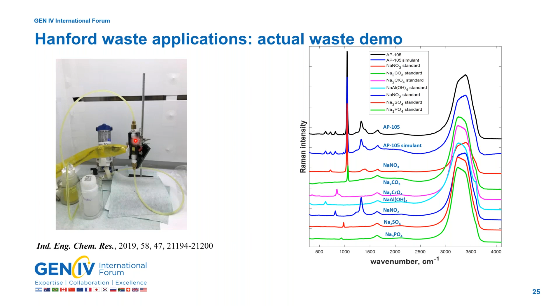So we've taken this AP105 and we put it in one of our flow cells, or in a flow loop. This is the AP105 waste here. It's straight AP105 waste. It's not been processed in any way except to take the cesium-137 out by ion exchange so we can have it contact handled in our open-face rad hood. So we have a pump that we're pumping it through our flow cell. This is a cuvette flow cell. We have a Raman probe. This is fiber optically coupled back to our spectrometer. We're able to shine light into our flow cell and measure the AP105.